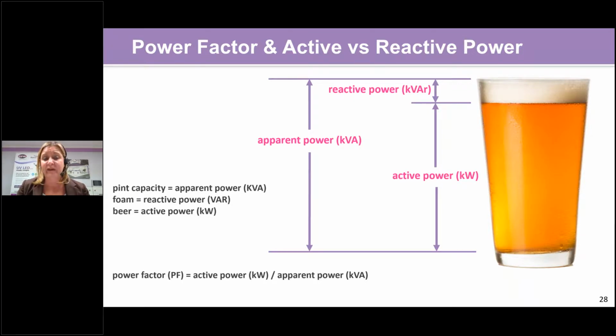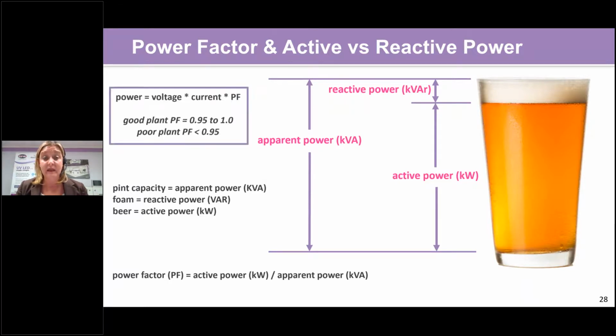We calculate power factor by dividing the active power by the apparent power. The best it can be is 1. 0.95 to 1 is very good; less than 0.95 is bad. If your plant has a power factor of 0.9, 0.8, or 0.7, it is costing you more money to run your equipment. You can do power factor correction in your plant, and that will lower your electricity bill.